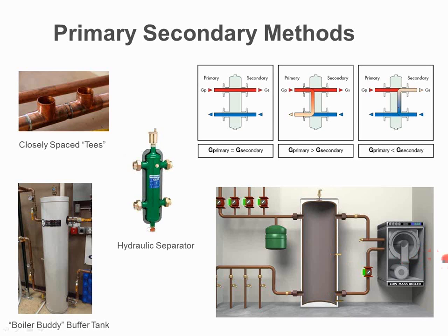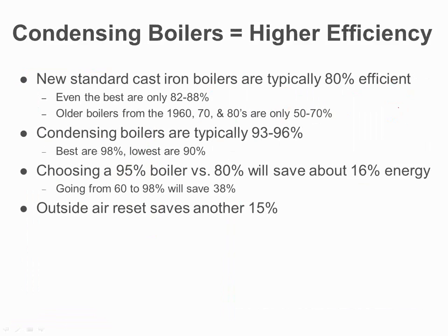A hydraulic separator is just another method of doing it. They're very popular in Europe. It is doing the same thing as a buffer tank, just a smaller version. Your easiest, low-cost way is the closely spaced T's. You absolutely have to do that. The hydraulic separator is just a fancy way of doing the closely spaced T's. And the boiler buddy is nothing more than a hydraulic separator that also gives you that buffering capacity that Bill was mentioning. So depending on your project, you may do it any one of those different ways.